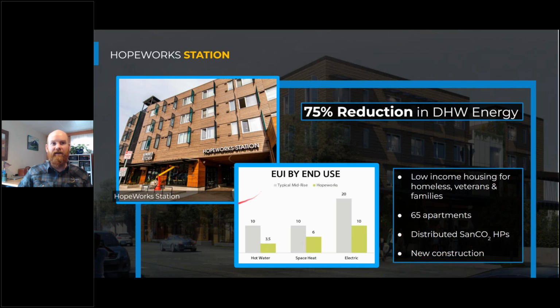So we can see our hot water usage over here. The typical mid-rise is coming in at about an EUI of 10 for that task, that load. We reduced this to 3.5. There are also other measures. We implemented split system heat pumps here for space conditioning, space heating, and we're able to reduce that from 10 to 6. And then other electrical measures on garage fan control, lighting optimization, ventilation, and other aspects of the building. We're able to reduce that load from the baseline of 20 to about 10, so cutting that in half. All in all, this ended up being a really efficient building, and it's been in operation for a few months now, so I'm really looking forward to watching this in the future and seeing how these systems are working in a few years.